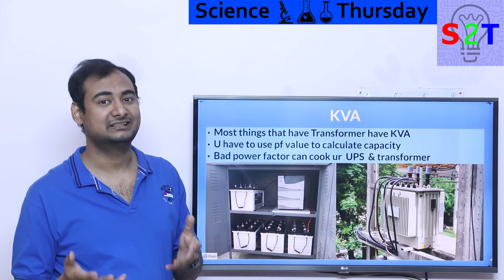And bad power factor, if you are ignoring it, in the worst case scenario, you can simply cook all your power providing equipment, be it your generator, be it your transformer, be it your inverter. So this is something that you have to pay attention to, and it also applies to UPS. Inverter, UPS, they are interchangeable in this context. So this was my presentation on power factor.